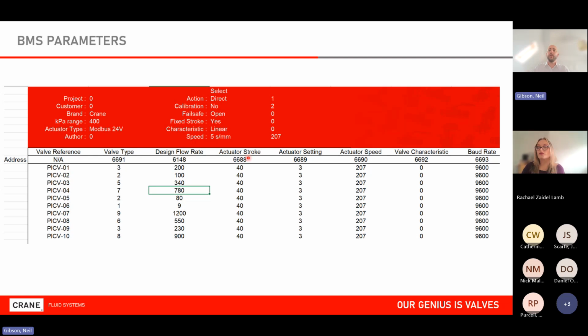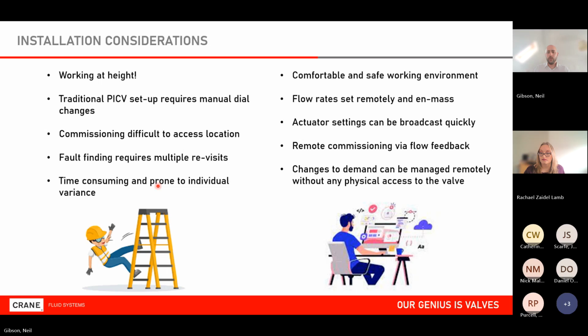But what we can do is we can plot and we can show, I haven't got examples here, but if you're interested, we can pick it up separately. If we set it to a reduced stroke length, I'll pick 50% as an example to define that design flow rate. We then drive that valve from 0 to 10 volts, so 0 to 100%, and watch if we still maintain that equal percentage curve, which in this case we do because the algorithm's built within the unit. So we still maintain that rangeability at reduced strokes as well. Thank you. No problem.